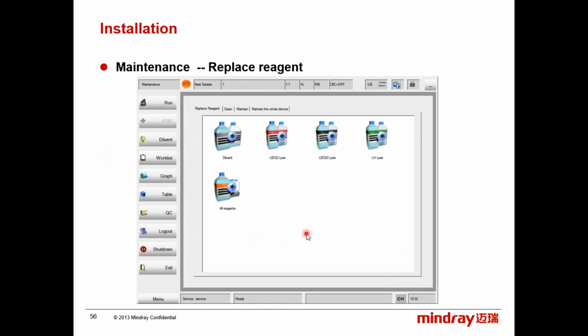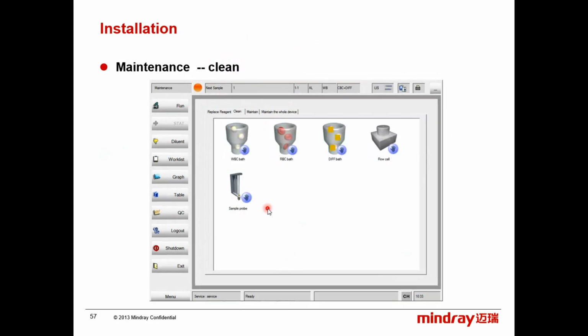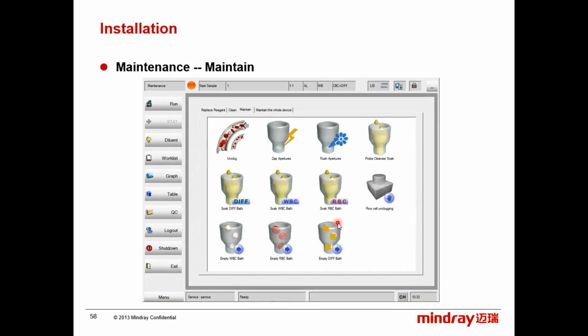This is to replace the reagents from the maintenance. What does it mean, replace? It means prime, okay? This is to clean: WBC bath cleaning, RBC cleaning, diff bath cleaning, flow cell cleaning, sample probe cleaning. This is for maintenance, okay? You can unclog, zap apertures.